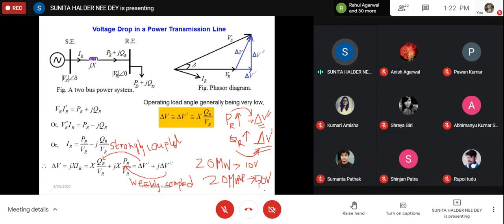If you change delta very small, 10 degrees, you will be able to transfer 20 megawatt power. But keeping the sending end and receiving end voltage same, if you want to transmit 20 MVAr power more, that means increase the reactive power, then you have to increase delta far beyond 10 degrees, because delta has very weak coupling with the reactive power.